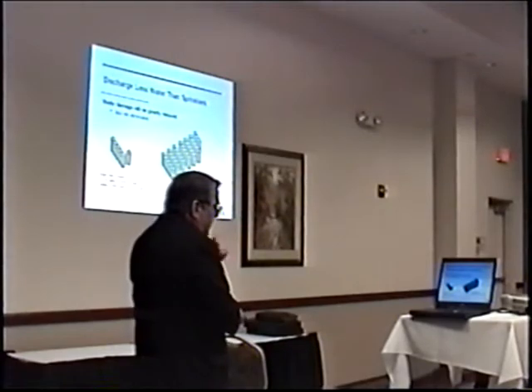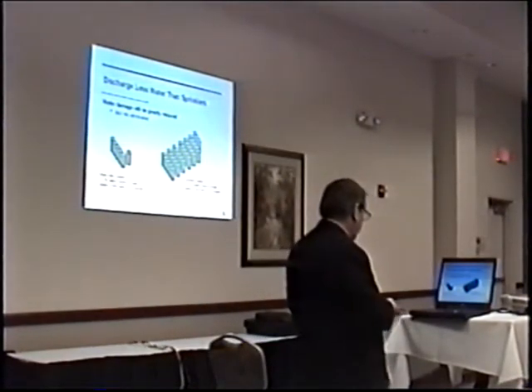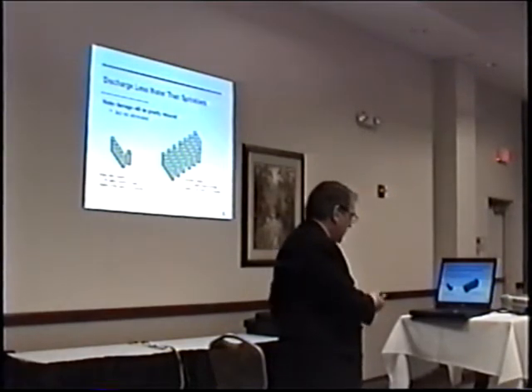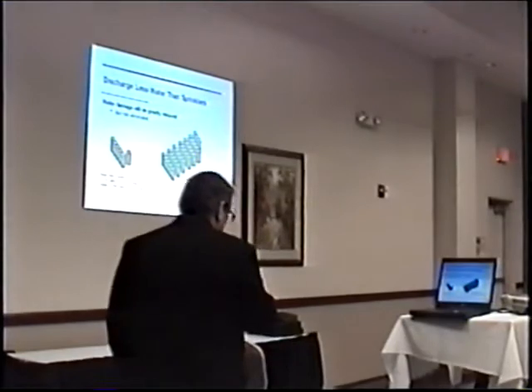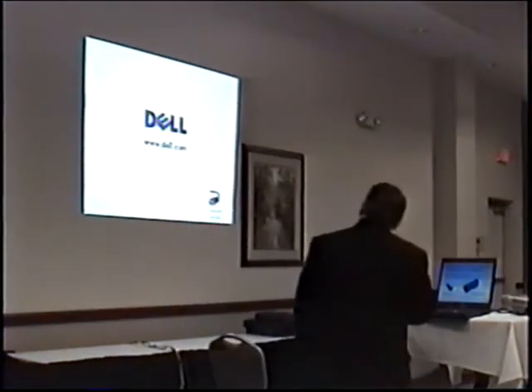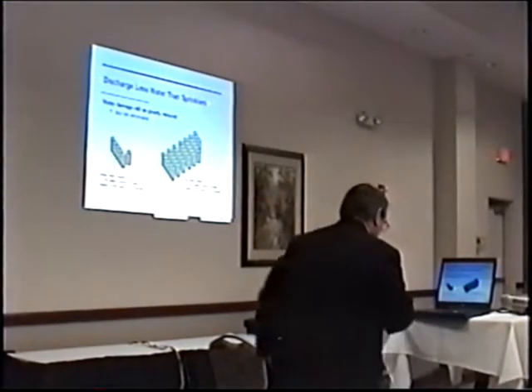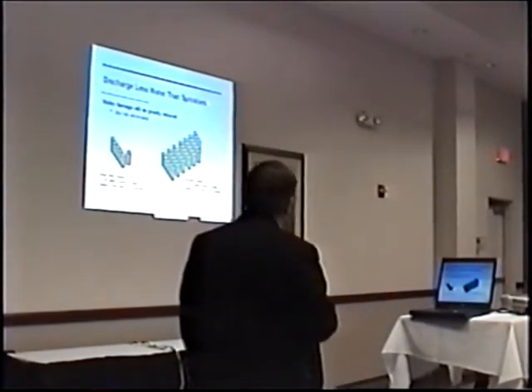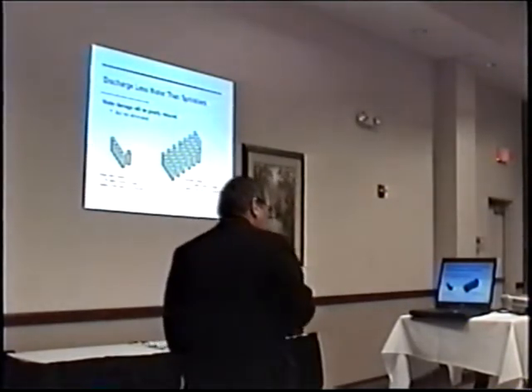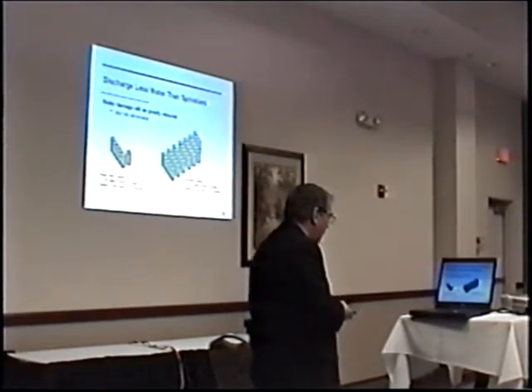Using standard sprinklers, basically four sprinklers located around some burning books on the shelf. And I compared it to the amount of water discharged by a system that I designed and tested at the University of Maryland for the same rare book vault.